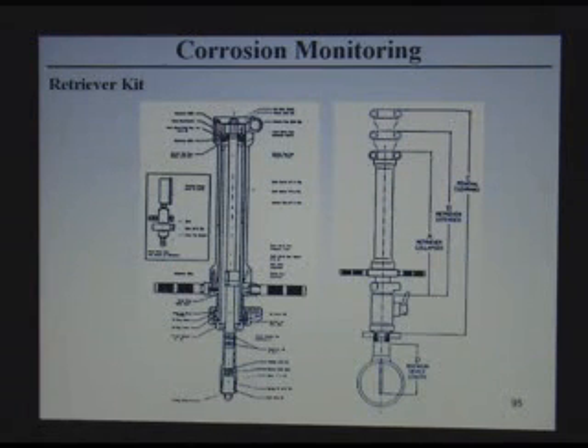These are the tools used to install and remove the coupons or corrosion probes on a stream without shutting down. They hook up to the fittings on the pipe, and once hooked up, you remove the coupon and close the valve, and you're back in the stream. You take it out, weigh it, etc. If you'd like to replace it, you put a new one, hook it up, open the valve, take the pressure, insert it inside, and close the valve.